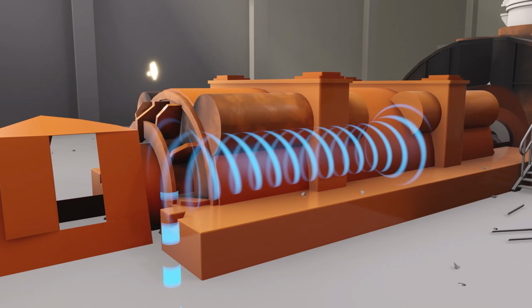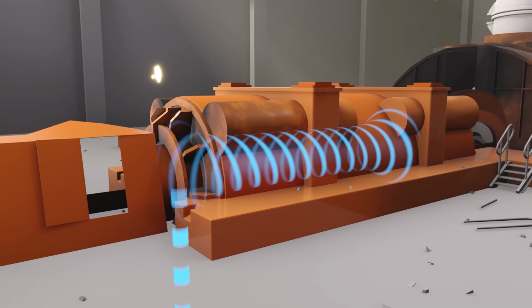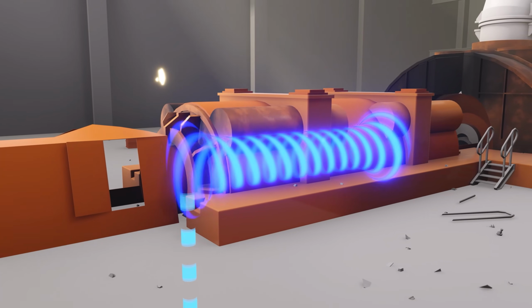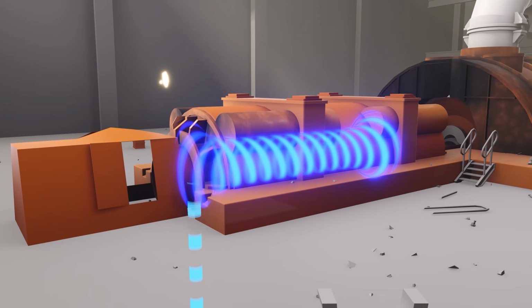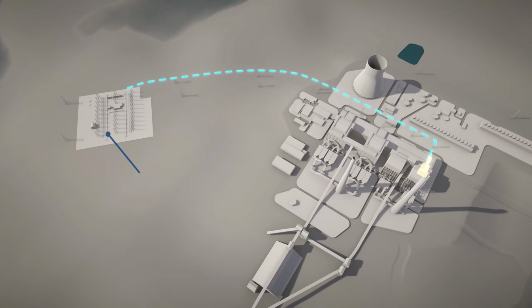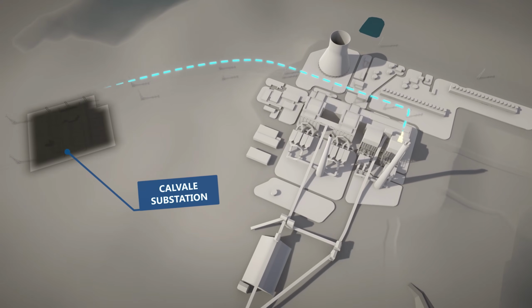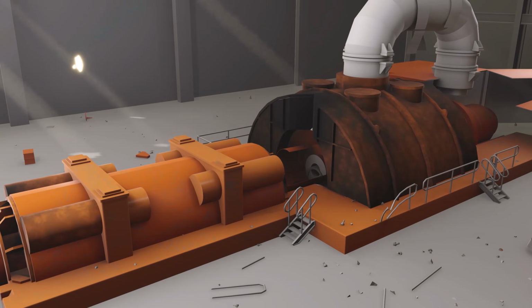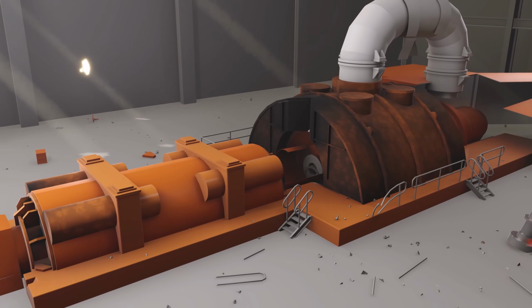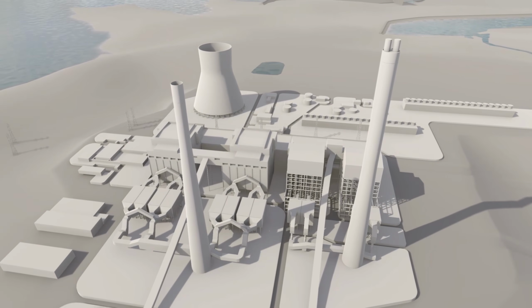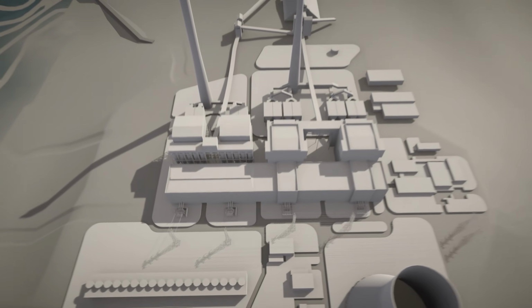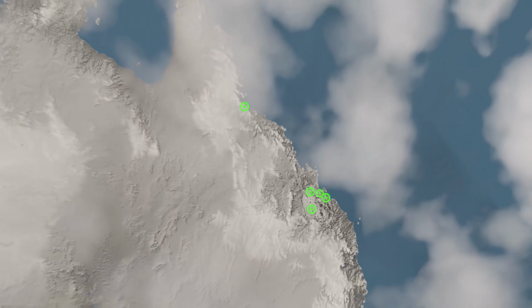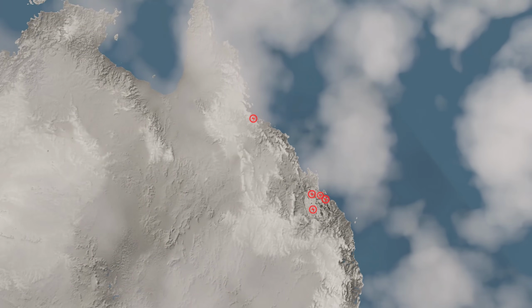With the generator still connected to the grid, large electrical arcs start to form, vaporizing the copper conductors, causing it to pull a massive 300 megawatts and over 1,400 megavars from the grid, nearly 3 times its rated export power. After 40 seconds of this, the arcing causes an electrical fault which is detected at the Calvale substation, leading to its protection systems operating automatically, finally disconnecting Unit C4 from the grid. By this stage, the generator and generator transformer are destroyed. The remaining people on site are then evacuated with no loss of life. But the incident destabilizes the grid, initiating a cascading failure that trips 9 major generator units across multiple power stations in Queensland.